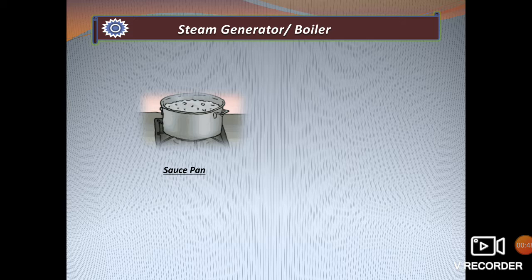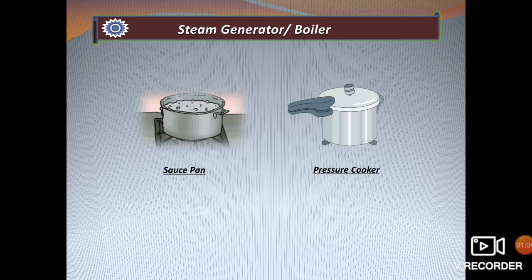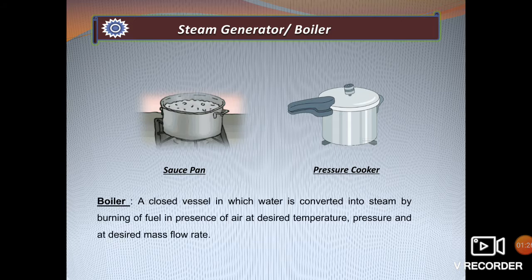To understand what a boiler is, let's consider an example of water boiling in a pan. The boiling point of water at atmospheric pressure is 100 degrees Celsius or 212 degrees Fahrenheit. By pressurizing the boiling system with an airtight seal, we can increase its boiling point — this is how a pressure cooker works. This same concept is used in boilers. A boiler can be defined as a closed vessel in which water is converted into steam by burning fuel in the presence of air, at a desired temperature, pressure, and mass flow rate.